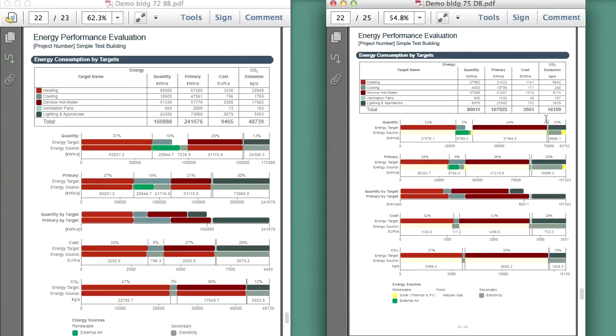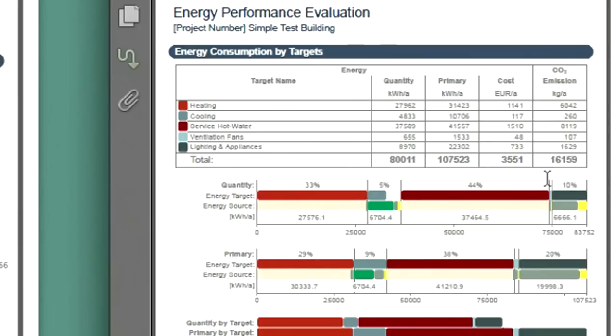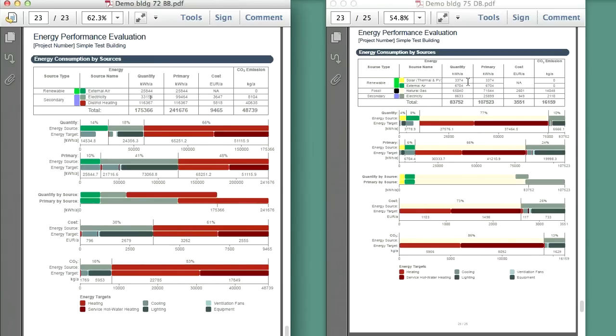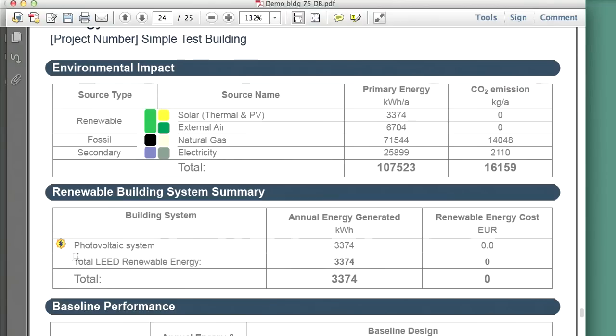Let's display the energy consumption by targets diagrams for both design scenarios. Please note that the amount of total required energy reduced. In the case of the baseline building on the left, the heating is provided by district heating. In the case of the designed building, a more efficient and reduced-capacity heating system is used — the on-site central heating boiler is the main heat supplier with local backup systems installed where necessary. The energy consumption by sources diagrams show a massive reduction in electricity demand, and 40% of this demand can be satisfied with electricity produced by the PV panels on-site.